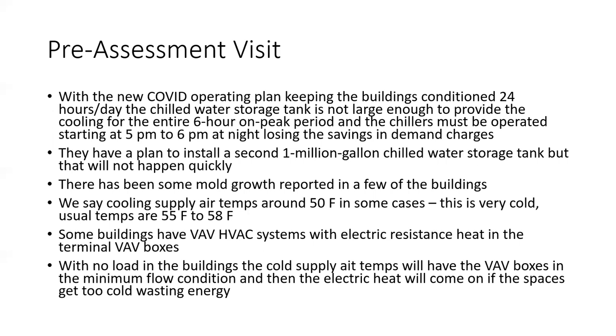Well, so if you're running this really cold supply air, with no load, no people, very few lights on, you would assume that the box would go to minimum position. And then if it was still too cold, you'd be heating it back up again. So it may be that they're cooling it down too cold so they can heat it up again later in the space. That's something else we'll need to try to look into.